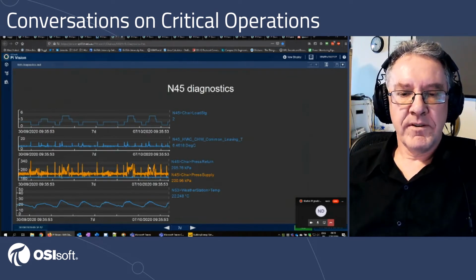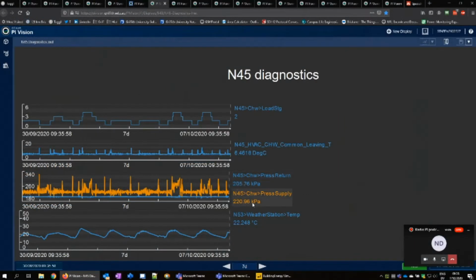N45, chiller. This is our chiller compound. We can see the field pressure, the supply and return pressures for our chiller plant. We can see the chiller stepping up as we add chillers, as we load up in the chiller house over time, so we can see how it's behaving over time. We can look at the external temperature coming in as well. Here we're bringing in data from the building management solution, so that's the load stages. We're coming in from the weather station on another building. We've got pressure sensors in the field on the ring main. Our main chiller plant in Nathan is a primary tertiary setup, which is a very odd configuration. The chiller pumps actually move all the field water, so it's very sensitive to pressure on supply and return to make sure we get water out to the buildings.